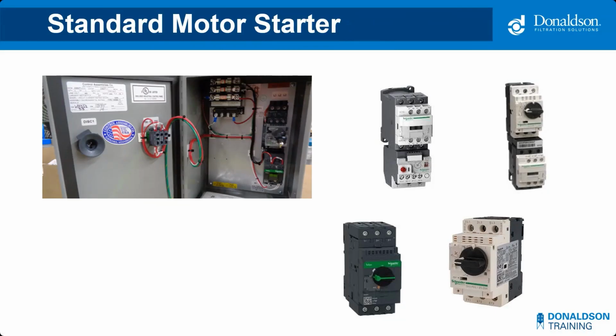The motor immediately runs to full speed. The stop push button is going to open the contactor, which will open the circuit to turn the motor off. And this is the simplest of just on-off control without speed control. The overload device provides a thermal protection. When the motor is drawing excessive current, the wires are going to heat up. The overload protection will open the circuit to protect the wires, which ends up protecting the motor and the equipment.